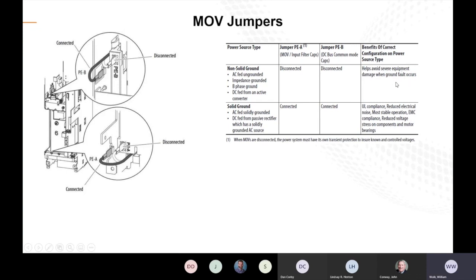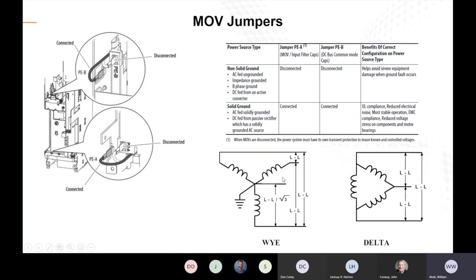Here's just a couple of the benefits if you have the correct configuration too. And also, it's important to note that if you don't have these MOV jumpers, or if you do have them installed and you don't have it based correctly on the type of grounding situation that you have, then that could cause premature failure of your VFDs. But here's just a couple of the types of groundings you can have. You have a Y delta.